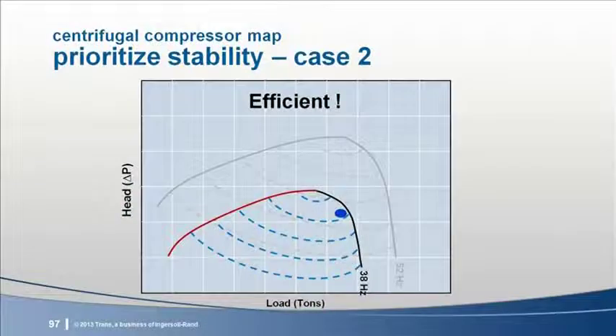A chiller's control number one priority is to safely meet the leaving chilled water temperature, so the controls would immediately begin to reduce the inlet guide vane position and the compressor speed to restore the proper chilled water temperature. In a short period of time, the load would be back under control. This is all fine, and the chilled water load would be met without any problem to the system, but any time the chiller controls are forced to chase significantly unstable tower control or unstable chilled water return temperature or flow is a time when the chiller and system are not operating at peak efficiency.